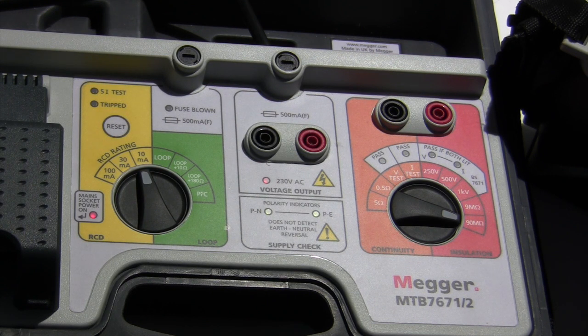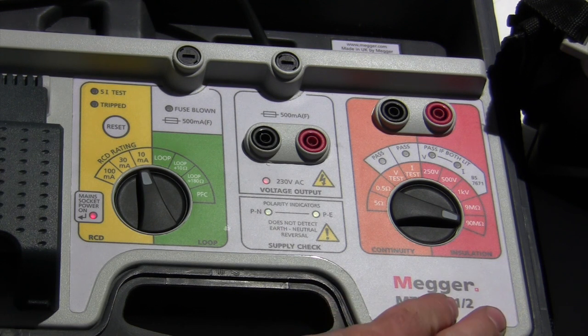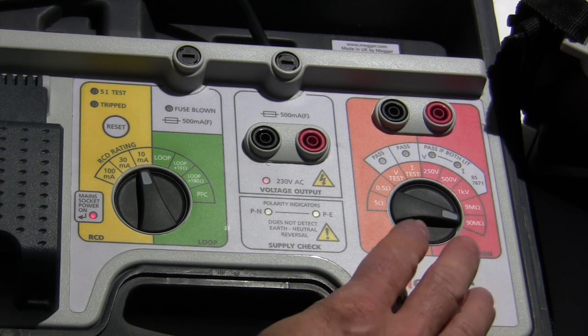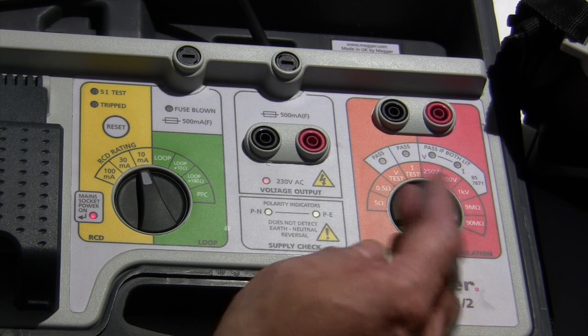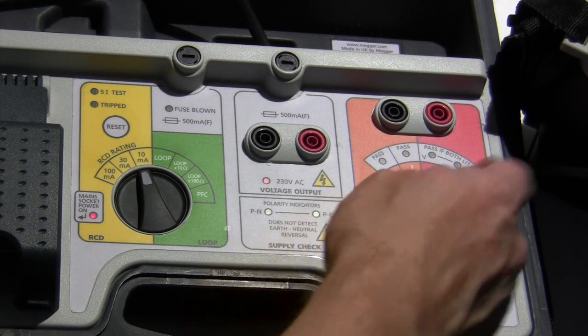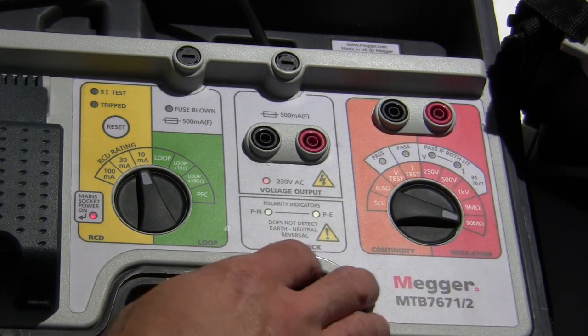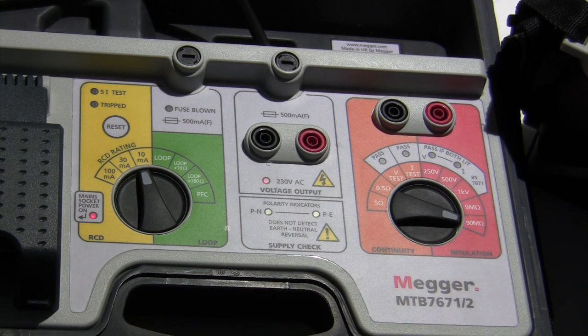So let's have a look at this from right to left. We start off with the dead tests. We've got continuity and insulation on this side, so this will obviously send out some resistances which should match what we see on the screen of the tester. Insulation resistance testing, obviously when we squirt a DC voltage at 250, 500 or a kilovolt into the thing, then we expect to see certain numbers come back.